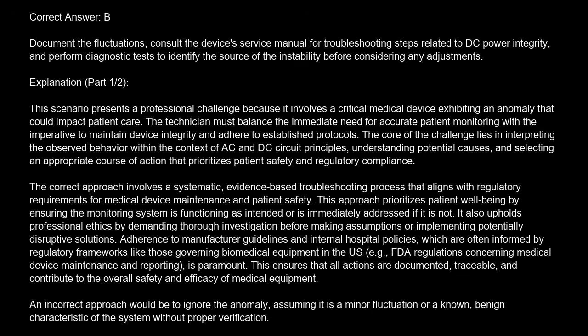The correct answer is B. Document the fluctuations. Consult the device's service manual for troubleshooting steps related to DC power integrity, and perform diagnostic tests to identify the source of the instability before considering any adjustments. Explanation. This scenario presents a professional challenge because it involves a critical medical device exhibiting an anomaly that could impact patient care. The technician must balance the immediate need for accurate patient monitoring with the imperative to maintain device integrity and adhere to established protocols. The core of the challenge lies in interpreting the observed behavior within the context of AC and DC circuit principles, understanding potential causes, and selecting an appropriate course of action that prioritizes patient safety and regulatory compliance.